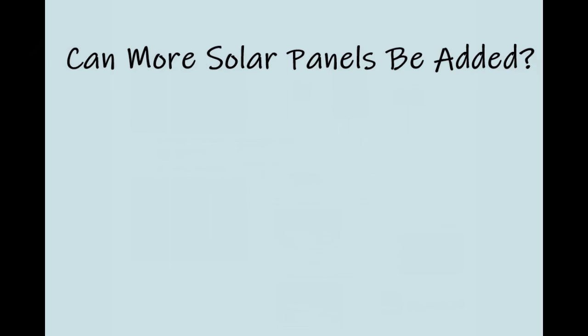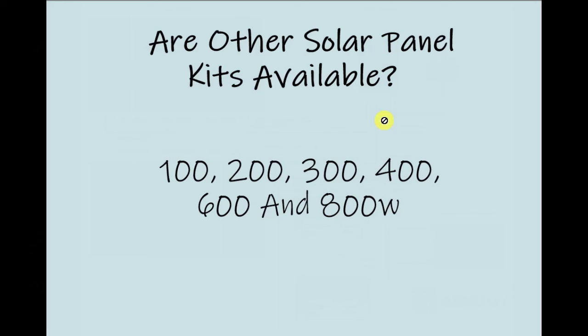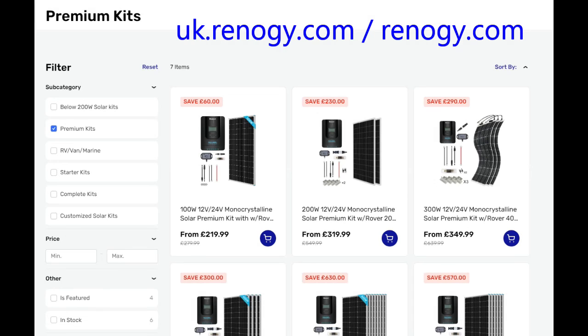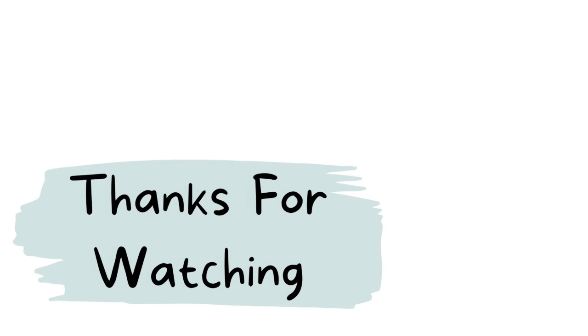Can more solar panels be added? Renogy also offers an 800 watt kit, which is essentially the same as the 600 watt kit but with two extra panels and the same 60 amp controller — series one has four panels and series two has four, still with the parallel connection. For other panel configurations you would need to do cable and voltage/amperage calculations to confirm the charge controller can handle the array. All kit options — 100, 200, 300, 400, 600, and 800 watt — are available on the Renogy website, with a link in the description.